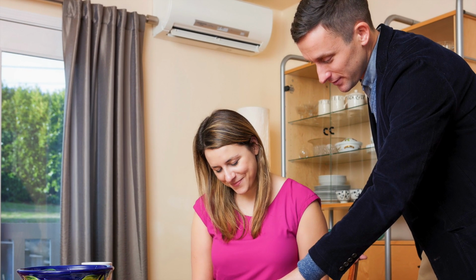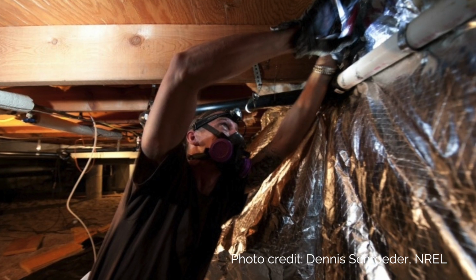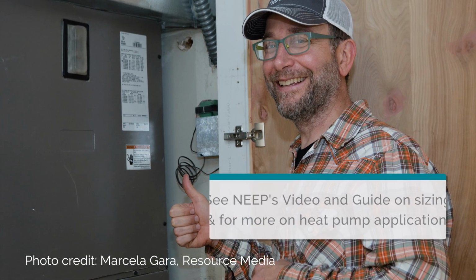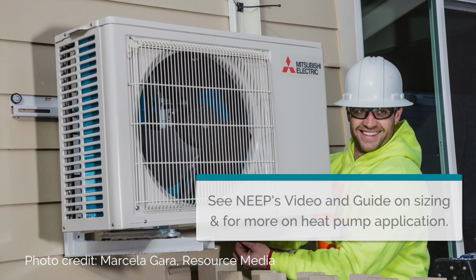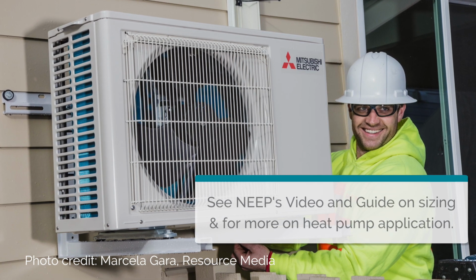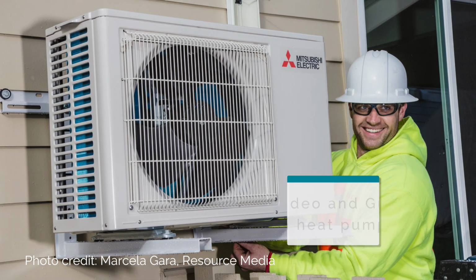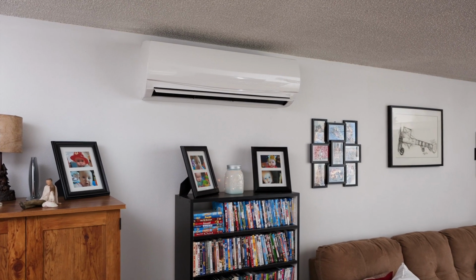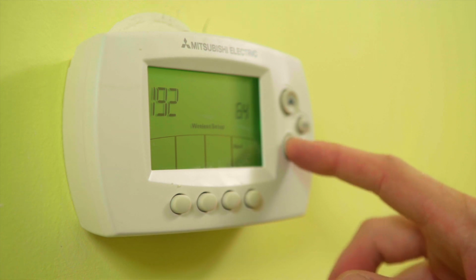master bedroom. If the customer decides to keep their existing heating system as a backup, you have to understand how to right-size the new equipment. Undersizing the heat pump somewhat for the heating load may actually improve efficiency. When a heat pump serves a large area, mount a thermostat on the wall to sense the temperature in the middle of the space.